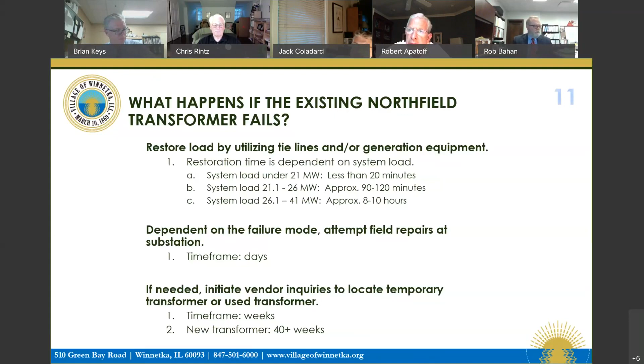Next slide, please. My predecessors and the previous village councils planned for two transformers at the substation. The transformer pad already exists for the next unit. They brought two transmission lines into the substation, along with the high voltage bus work and switching. What's left is the switchgear, which includes relays and protective logic, the transformer itself, and cabling from the transformer to the switchgear inside the building. Since the time it was designed and put into service, engineering staff has also identified that we probably need additional site modifications to reduce the risk of a single event impacting both units. Last year the clean agent fire suppression was installed in the building, and coming later this year, as I mentioned, Giovanni will be presenting the design work to install a firewall between the two transformer locations.